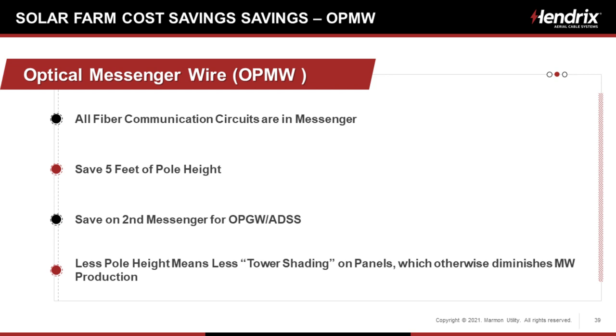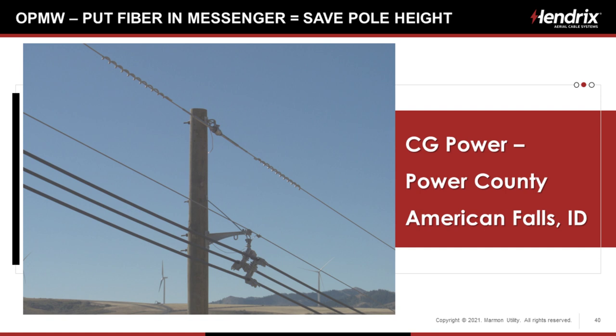The next thing, we talked about optical messenger wire. Well, all of these facilities, we need fiber, we need communications. Here we have the ability to put all of those fiber communications right into the messenger. That's going to lead to saving 5 feet of pole height. We might save on a second messenger if we can put all the communications in that one messenger. So less pole height means less tower shading on panels, which otherwise diminishes megawatt production.